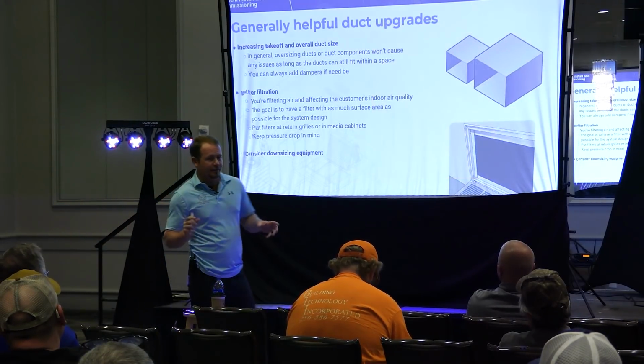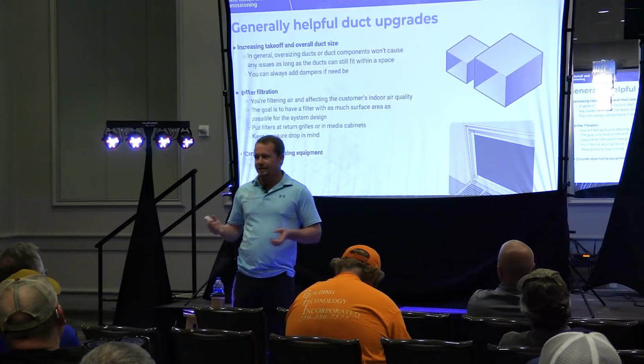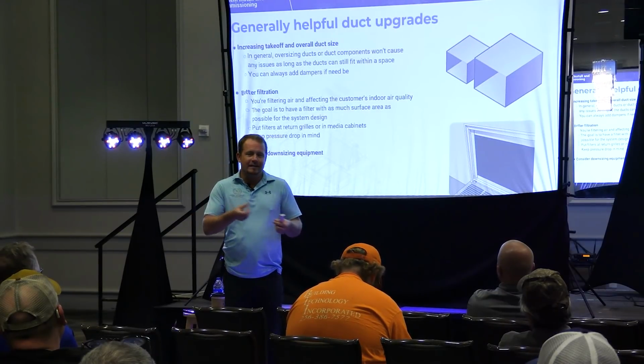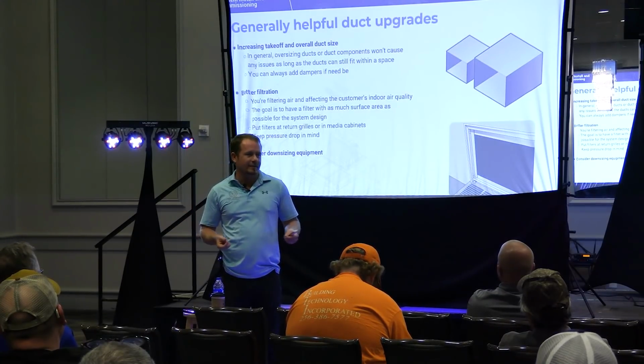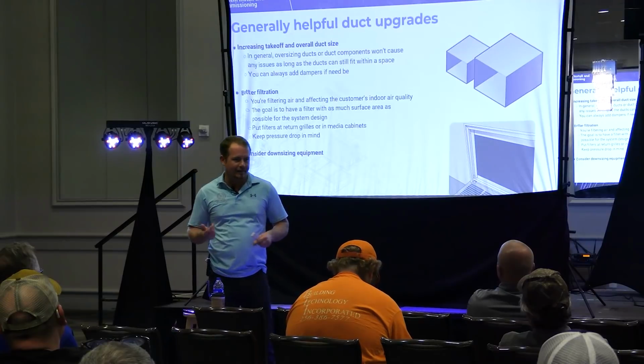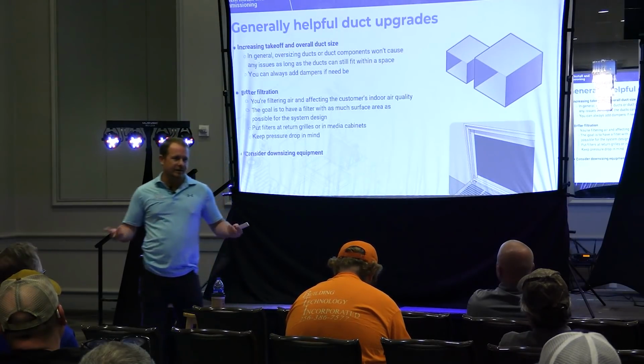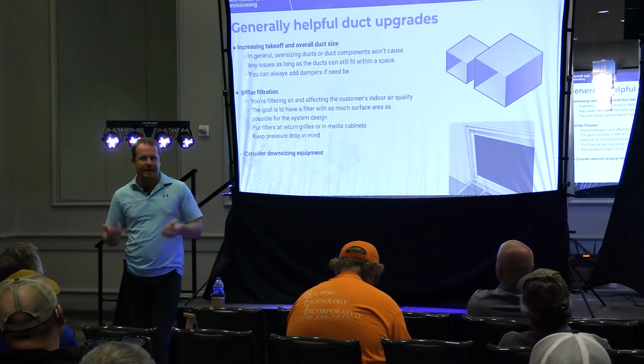That's the kind of the thing about 1-inch filters in the factory filter slots, is they're terrible. Like, have you seen the gaps around a filter in a Carrier unit? I mean, it's ridiculous. So much air can go around that filter. So even if you put a good filter in there, it's just gonna go around it, and that good filter is gonna increase static pressure and all that.